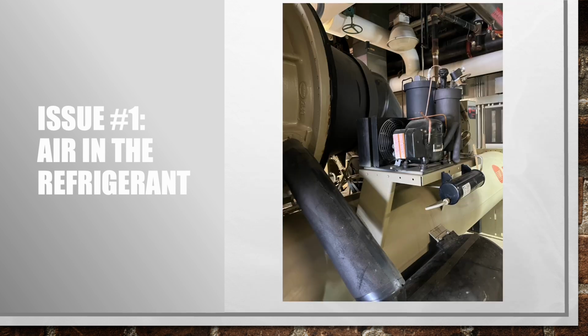If you think you have air in the system and you need to get it out to get the machine online, connect a recovery cylinder to the top of the condenser and go ahead and vent it off the top of the condenser into the recovery drum. Do it in a few second bursts, 5-10 seconds. Vent a little bit of gas off the top into your drum, and then check it while it's operating and see if that made a difference, if it seems like it's improved the problem, or if it didn't change anything. But it's pretty easy to actually test that.